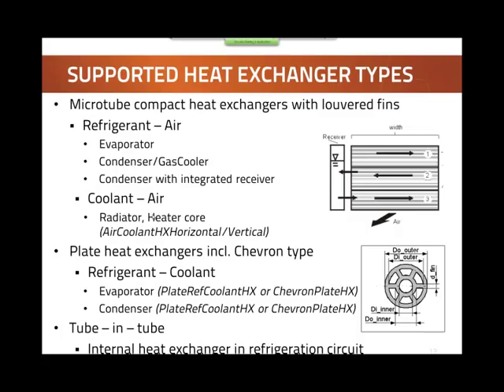This slide gives an overview of the heat exchangers supported by this library. The most important type is the microtube compact heat exchanger with louvered fins — all the geometry information is included, so you can parameterize such a heat exchanger with geometry values. We have these for refrigerant and air, which are typically used as evaporators and condensers in a refrigeration cycle. We also have the same type for coolant and air — coolant here is single-phase liquid — and they would be used for radiators and heater cores.